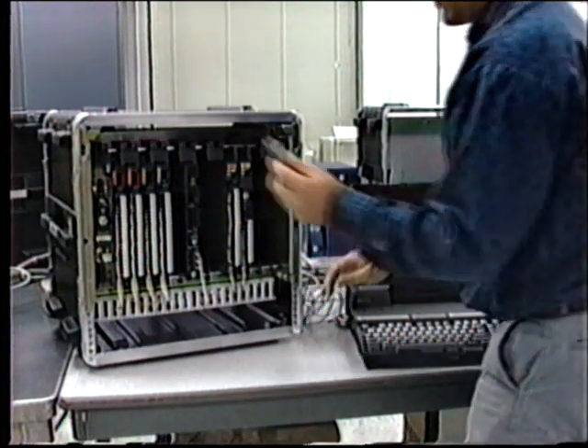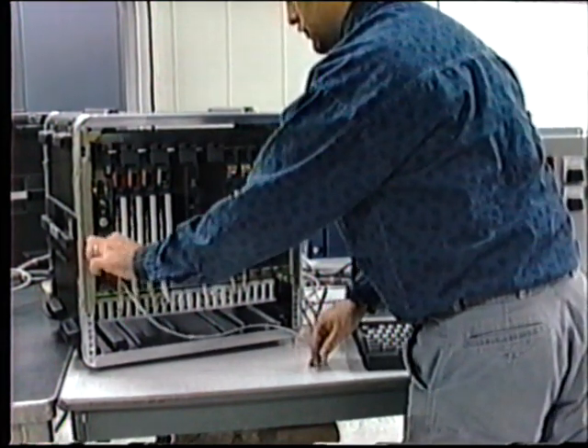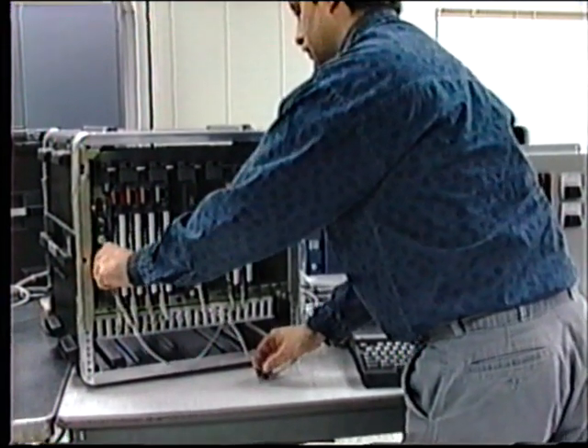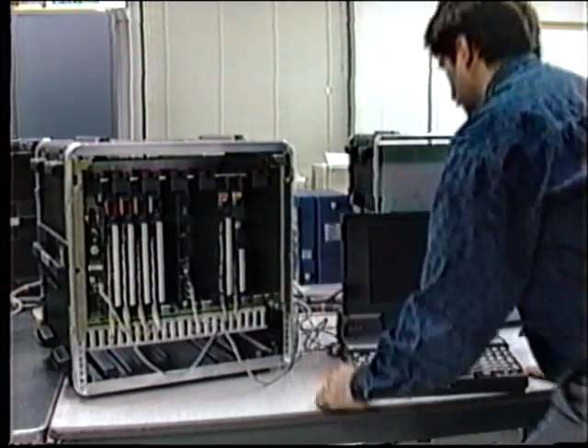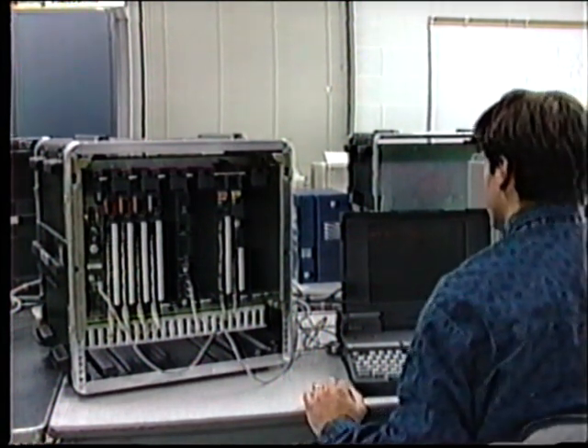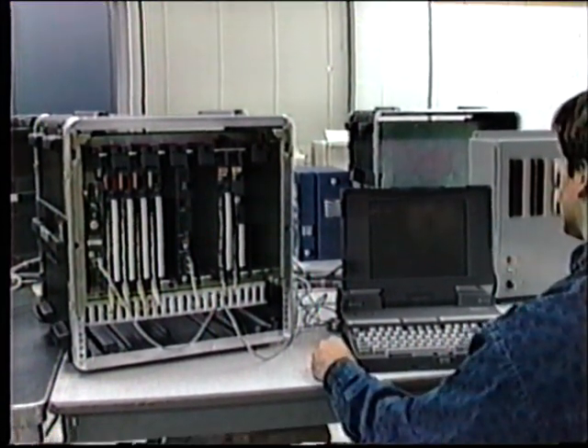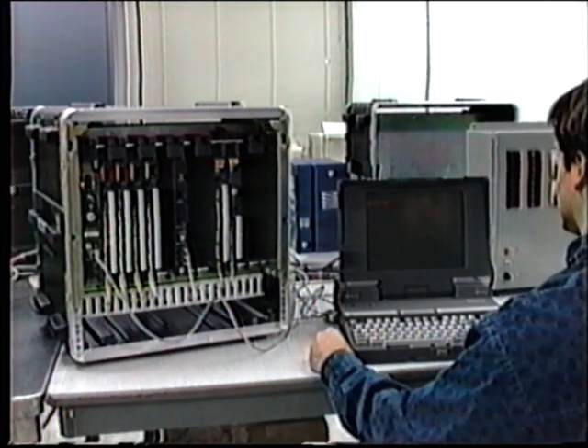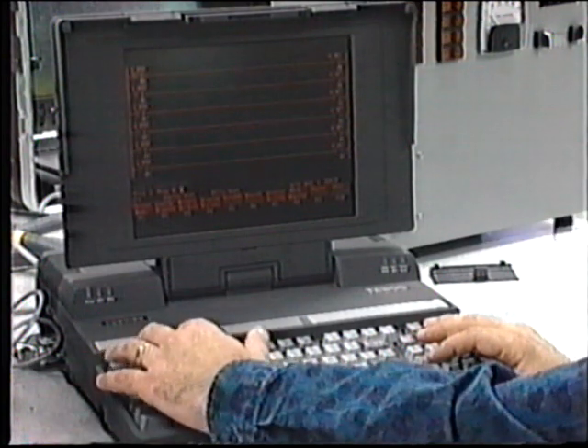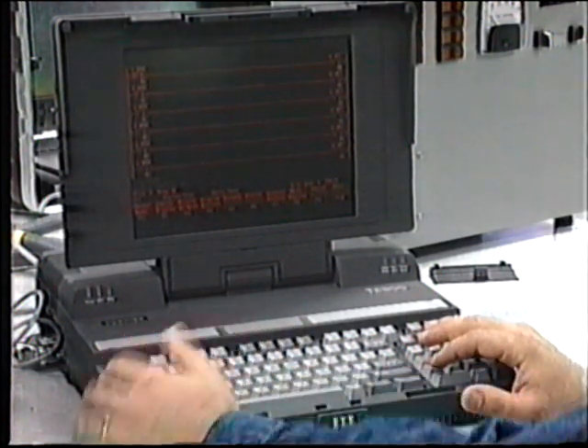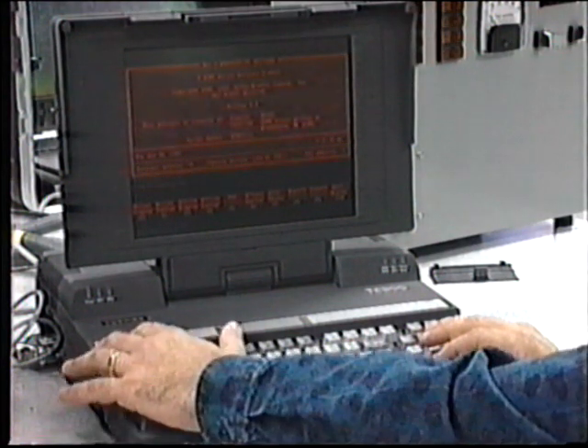In earlier segments, we noted that the PLC's logic is retained in the programmable memory, usually EEPROM. The instructions are stored in computer language, that is, binary code. In order to modify a program, or indeed to assemble a new program, we input instructions or commands to the controller from an external programmer. The programmer is actually a small portable computer which converts our instructions into binary form and enters this directly into the EEPROM. To make it easy for us, the programmer is equipped with a screen and a series of push buttons, each containing a specific logic function.